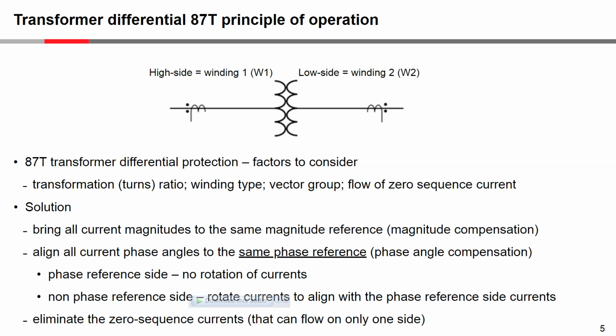On the phase reference side, there would be no rotation of current. So the current that is flowing in the primary network would be the same phase of current that would be entered into the 87T function. The non-phase reference side currents need to be turned or rotated to align with the phase reference side currents. And also we need to eliminate the zero sequence currents, which, as I said just now, can potentially flow on one side only.